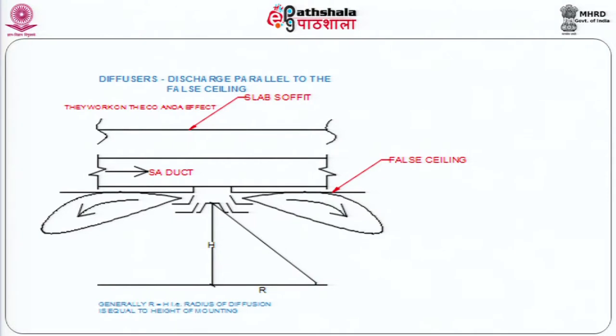This slide shows a diffuser in place of a grill. Diffusers have the advantage that they tend to throw air parallel to the ceiling in place of perpendicular to the wall, as was shown in the earlier slide. These are easier to make draft free. They call for a little extra ducting, but they are perhaps the best.